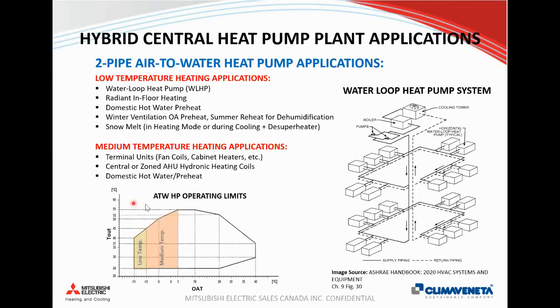Radiant in-floor heating is another good one. Domestic hot water preheat, ventilation preheat as well. If you can work with 35-degree supply temperature, you can do preheating of your ventilation air and then top it up on the air side with a backup furnace. And snow melting is another good application. Medium temperature, if you do need a bit warmer temperature, you're talking about fan coils, cabinet heaters, coils and air handling units.